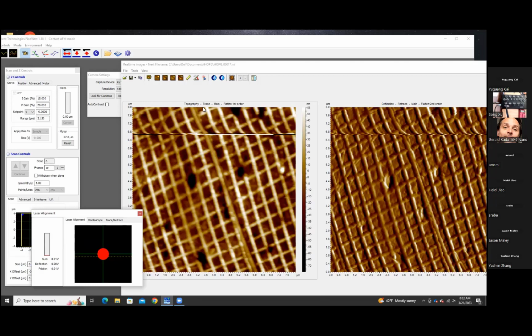Okay, I'm back. Now it's also connected to the breakout box. My first and foremost step is always to check the power supplies before I do anything else, because if there's an issue with the power supplies, nothing else is really going to matter. So in the middle of the breakout box, there's 3 BNCs. One's labeled positive 5 volts, one's negative 15, and one's positive 15. So we want to go ahead and check those voltages and see where they're at. They should be pretty close to 5, 15, and negative 15. If there's a significant deviation, this is going to definitely cause problems with your operations.